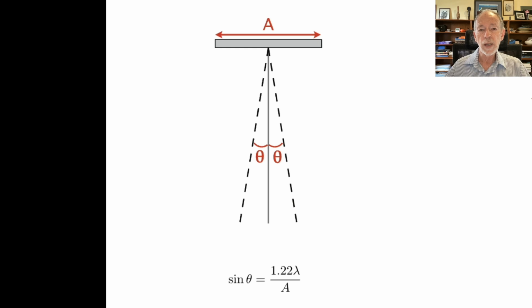The other parameter then is the aperture, the size of the area on the face of the probe which is transmitting and receiving the ultrasound. And you'll see that the sine of the diffraction angle is proportional to 1 over the aperture. This means the larger the aperture is, the narrower the diffraction limit will be, and therefore the better the focusing. So we basically want high frequency and a large aperture, and that will give us the best possible focusing.